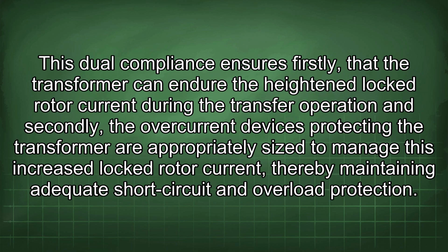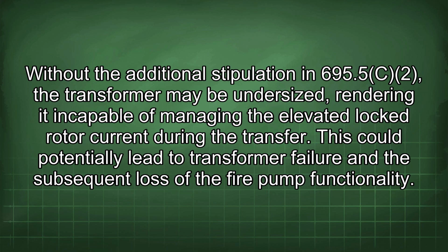This dual compliance ensures, firstly, that the transformer can endure the heightened locked rotor current during the transfer operation, and secondly, the overcurrent devices protecting the transformer are appropriately sized to manage this increased locked rotor current, thereby maintaining adequate short-circuit and overload protection. Without the additional stipulation in 695.5 C2, the transformer may be undersized, rendering it incapable of managing the elevated locked rotor current during the transfer. This could potentially lead to transformer failure and the subsequent loss of the fire pump functionality.